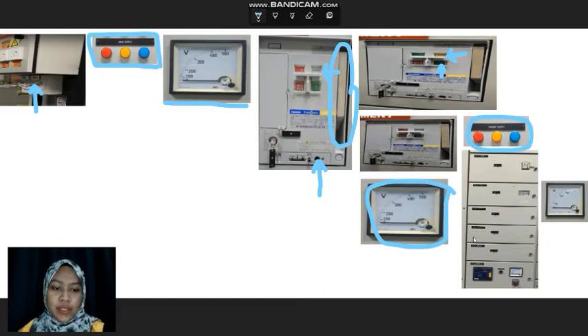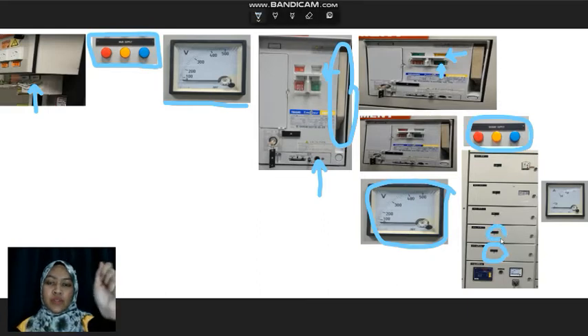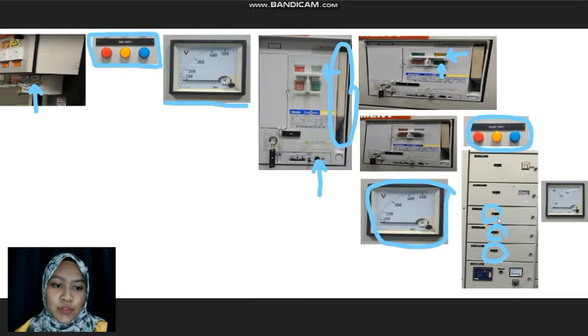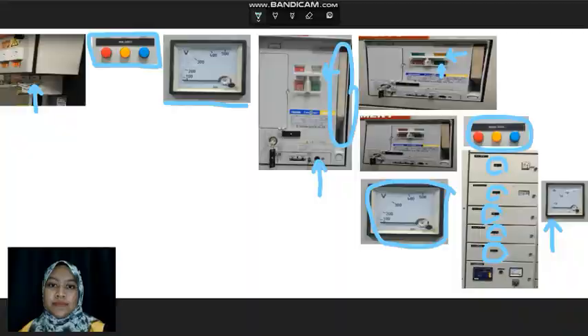Before we turn on the load, the MCCB, we must inform the consumer side first. After informing, we turn on the power factor capacitor and the MCCBs one by one, by pushing them to the left. After we turn on the MCCBs, we can check the current status of the system. Now MSB2 is energized and the supply is given to the consumer.